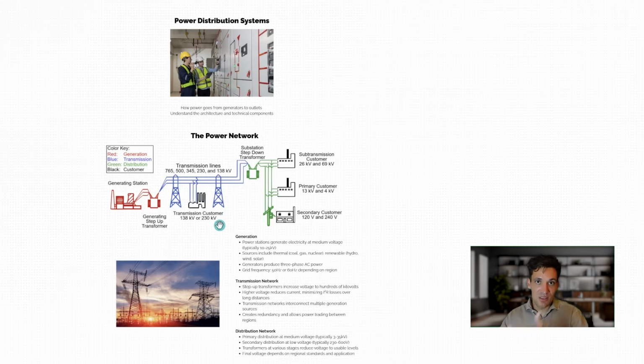And then this brings the power into the point where all our loads are. We then have a step down transformer. So we take the 500,000 volt input from the transmission lines and step it down to something like 11,000 volts. And this is how it's distributed through a system. So connected to the distribution network are our customers. You could have large industrial customers, like for example, a data center might connect directly to the distribution network at 26,000 volts, 11,000 volts or whatever. You could then have customers that connect on the low voltage side where there's already a distribution transformer that steps it down to 240 volts. For example, your house would connect at the low voltage side. You don't have a transformer in your house that steps down the voltage. That comes directly from the street supply.